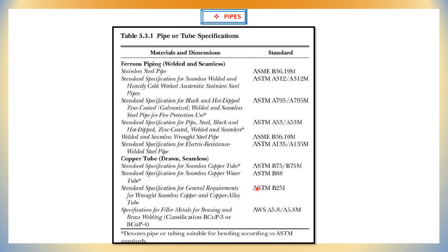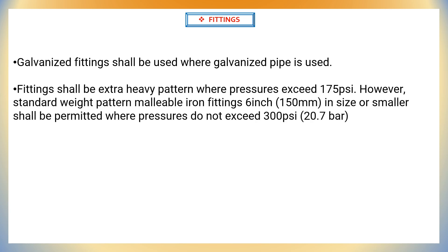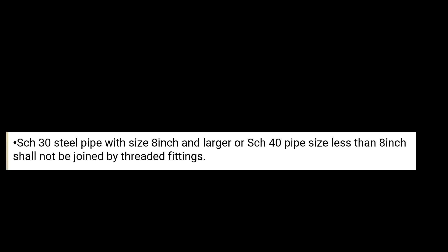The second major component is fittings. Galvanized fittings shall be used where galvanized pipe is used. Fittings shall be extra heavy pattern where pressures exceed 175 psi. However, standard weight pattern malleable iron fittings for 6-inch size or smaller shall be permitted where pressures do not exceed 300 psi. Schedule 30 pipes of 8 inches and larger, or Schedule 40 pipe less than 8 inches, shall not be joined by threaded fittings.